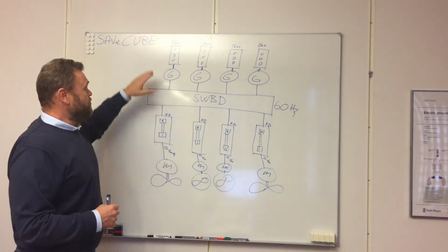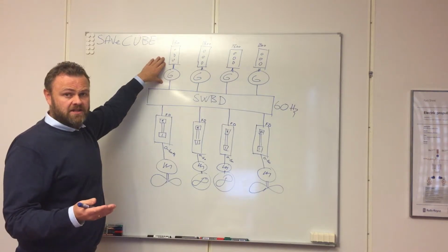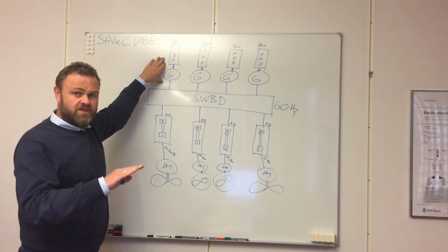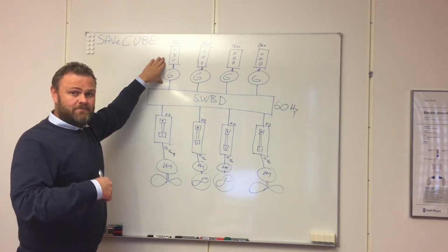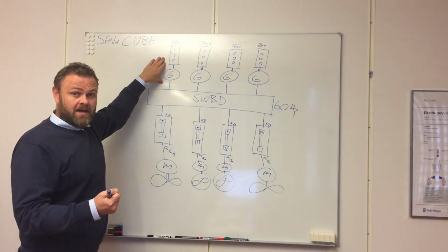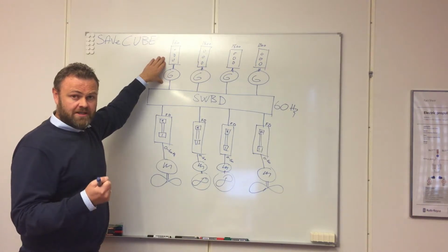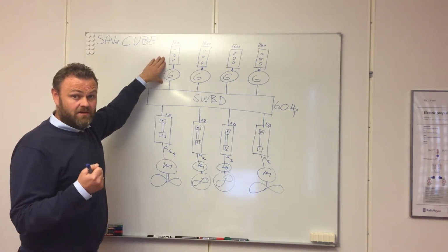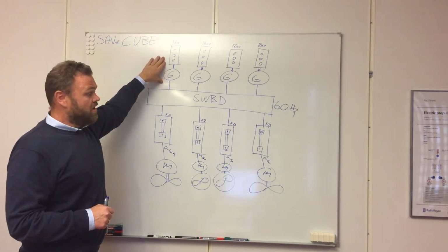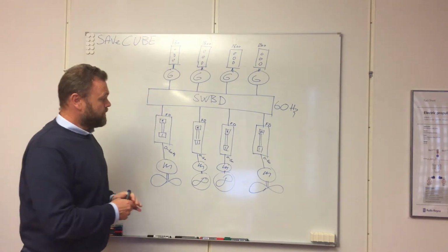Because in cases where you have 20-30% load on the engine, it would be very good if we could reduce the RPM, keep the combustion heat, and have a more optimum combustion in the engine and save fuel. Well, that is possible by doing something with the electric system.